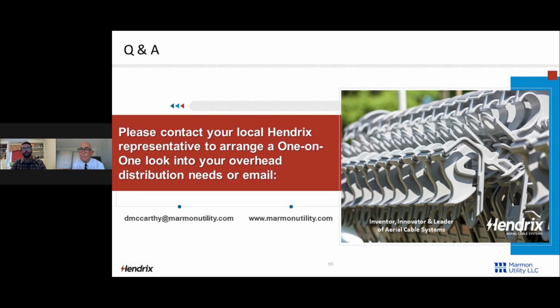Question from a utility here: can suspension clamps be used on tree wire? No, the answer is no. Suspension clamps cannot be used on tree wire. When we get up to 46 kV, we're still putting the polyethylene conductors on polyethylene insulators. When we get up to 69 and 115 kV, we no longer have those. So what we're doing is putting them on line post insulators with jackets around the conductor at 69 kV.